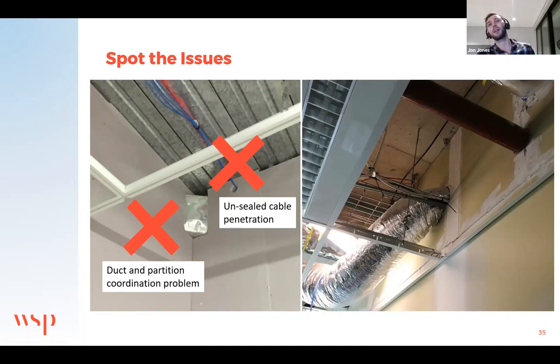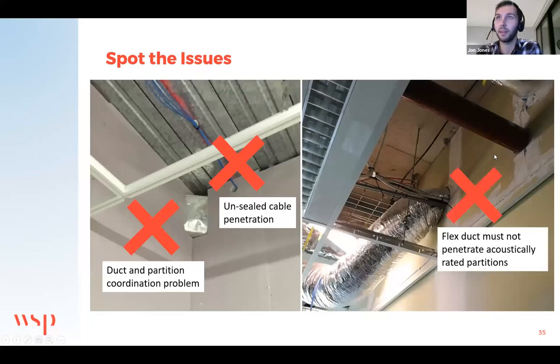On the right-hand side, we've got flexible duct at least here. The trouble we have with flexible duct penetrating an acoustically rated partition is that this sort of duct is not very good at insulating. If we go back to the two images about the sound insulation and the sound absorption, the sound insulation of this is very poor, so noise can easily transfer in and back out of this ductwork. So whilst we might have a solid wall here which is fit for purpose, if we've got flexi duct penetrating through it like this, you're quite likely to get noise breaking into the duct, transferring through the partition and breaking out again on the other side.